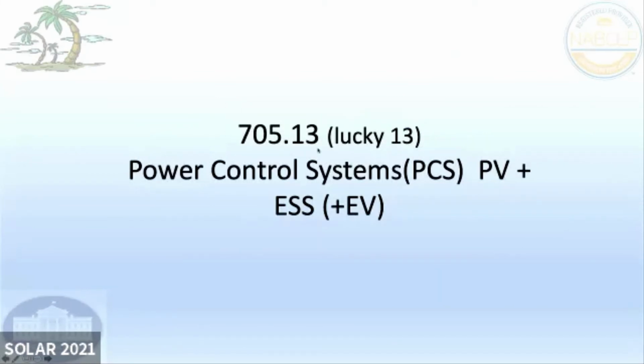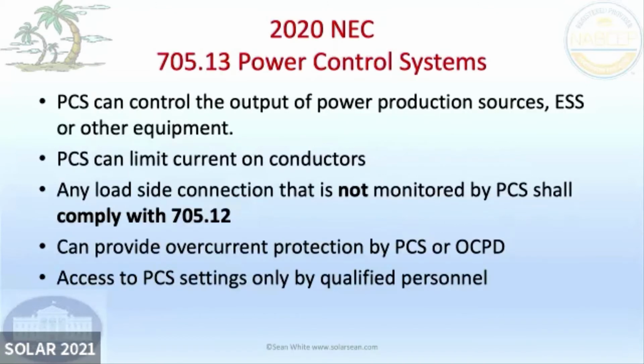So here we've got, I talked about this before, 705.13, and this is the one that's called power control systems. That could be a big change, but we're going to need to have some special equipment that deals with this. As long as you control the currents, and you'll have current transducers, and this is going to be a big thing, and they're starting to use it, then you don't even need to follow the load side connection rules or the supply side connection rules, because you can just control these with smart electronics, silicon chips in the brains of these systems. And you could limit the currents on all these conductors. So that's just a real neat thing that we have.